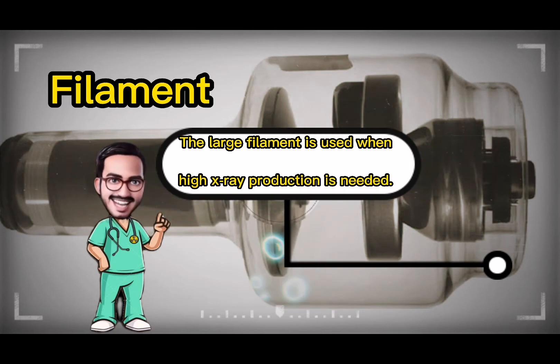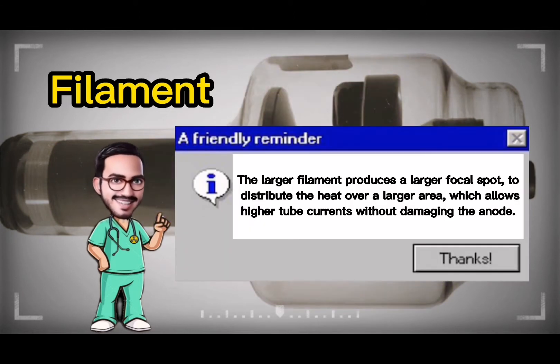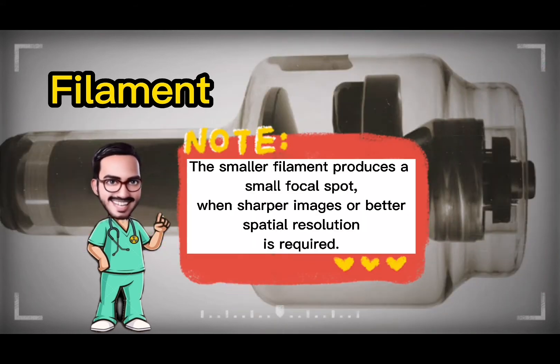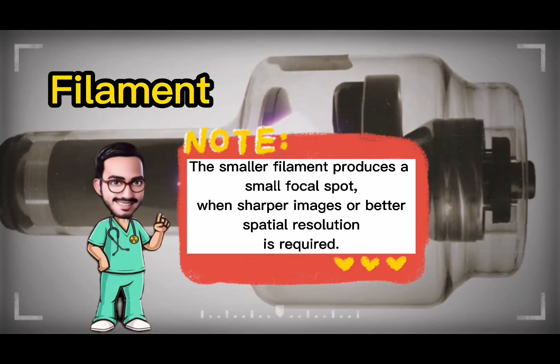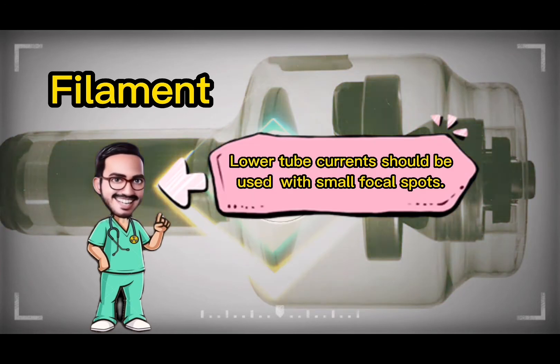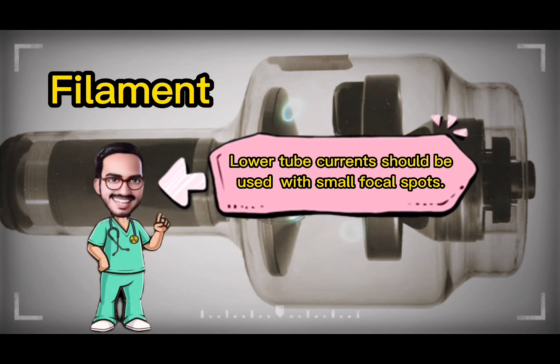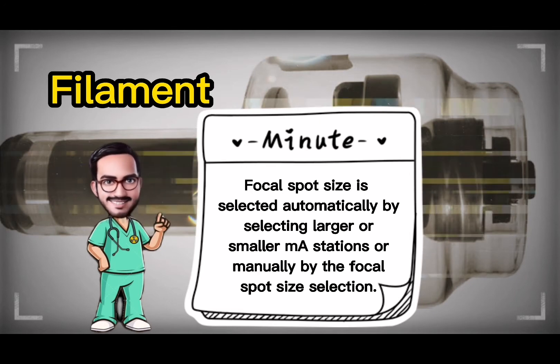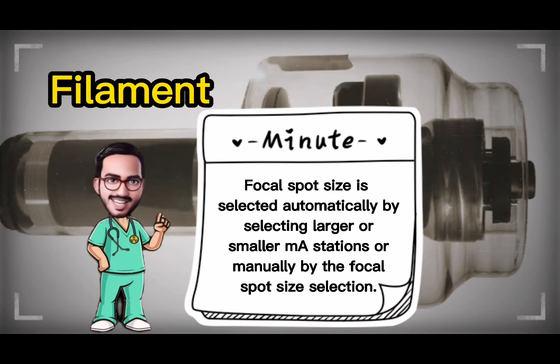The large filament is used when high x-ray production is needed. The larger filament produces a larger focal spot to distribute heat over a larger area, allowing higher tube currents without damaging the anode. The smaller filament produces a small focal spot when sharper images or better spatial resolution is required. Lower tube currents should be used with small focal spots. Focal spot size is selected automatically by selecting larger or smaller mA stations, or manually by focal spot size selection.